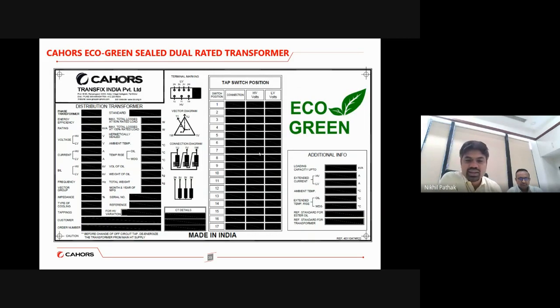So now you will be surprised to know that for mineral oil filled transformers, loading should be restricted to 80 to 90% of the capacity. However, we are offering dual rated transformers with this eco-green concept. Dual rating means a transformer can be offered with 110% of the rated capacity as enhanced loading capacity. However, with the change of insulation from class A to class B with natural ester oil, class B insulation even allows the loading capacity to go up to 120% of the rated capacity, which we have already type tested.